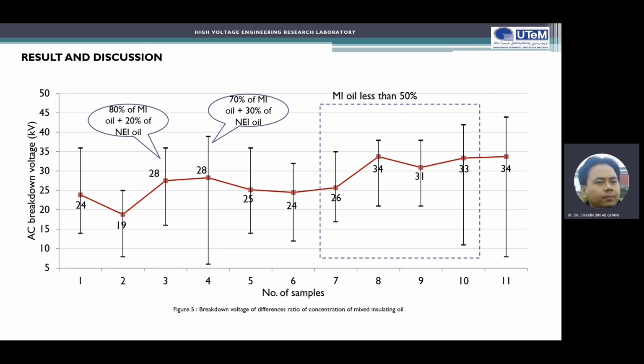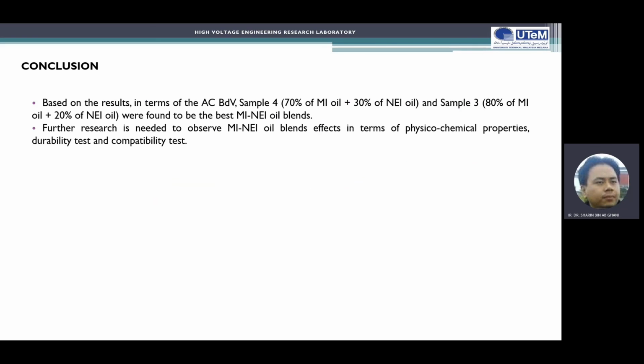In samples number 2 until 6, the highest breakdown voltage values come from samples 3 and 4. In sample 3, the composition of the mineral insulating oil is 80%, whilst the natural ester is 20%. Sample number 4 produced the same result, around 28 kilovolt, with 70% mineral insulating oil and 30% natural ester. So we can conclude that for AC breakdown voltage, the best blends of mineral insulating and natural ester oils are samples 4 and 3.